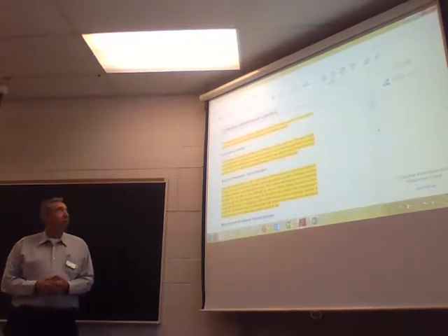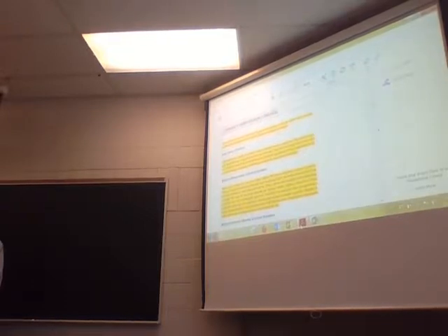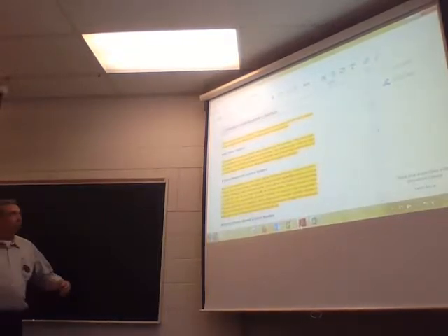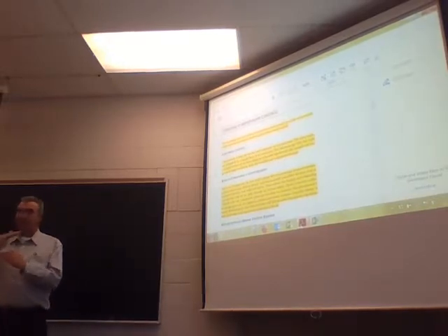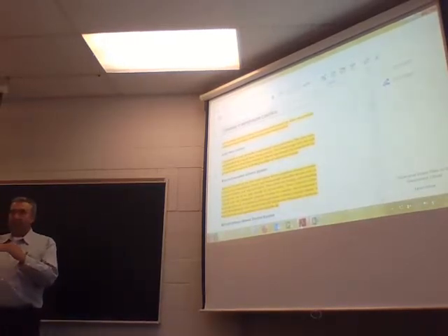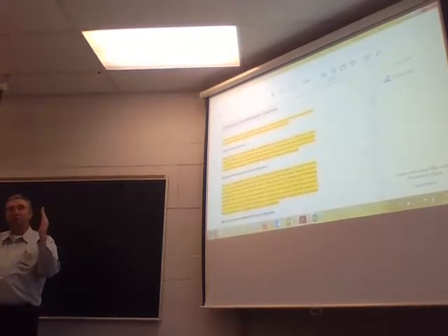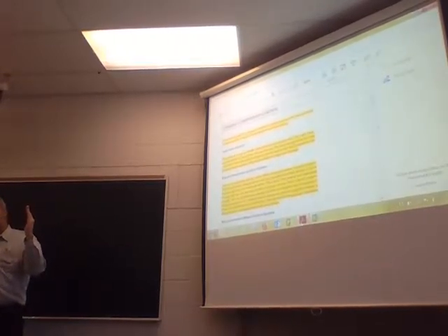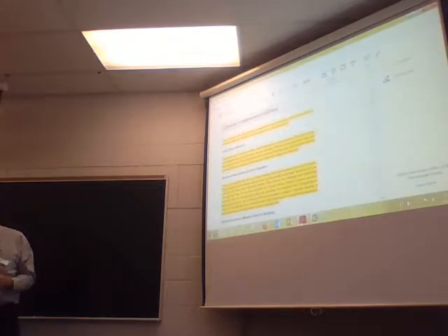So when we're talking about dynamic compressors, we always have to worry about surge. All right. So when we're controlling the inlet, my compressor is just going around, and then all of a sudden I get a quick reduction in load. It's going to close my inlet. The compressor now is not going to put out enough pressure. The pressure that's downstream will surge back. You understand how that works?